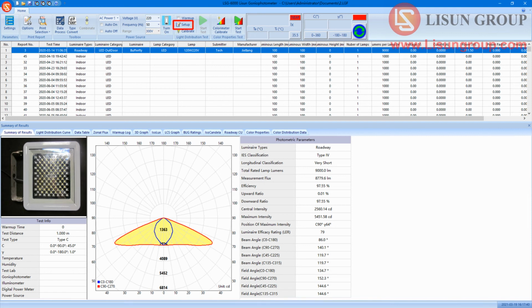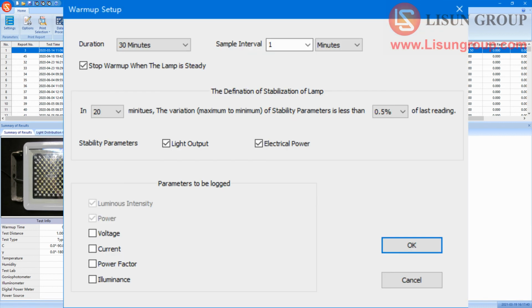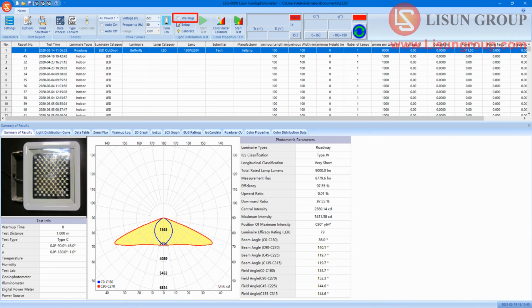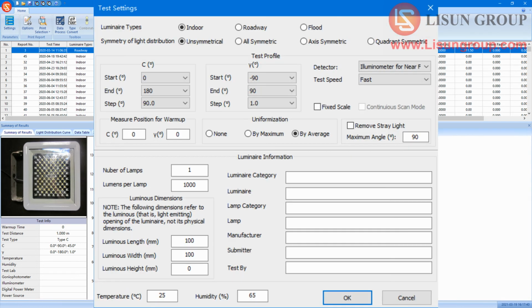Click Setup. Set warm-up parameters. Check warm-up if you need to preheat the sample before testing. Click Start Test. Choose luminaire types. Indoor and roadway are C-gamma tests. Flood is a B-beta test. Choose unsymmetrical if there are no special requirements.